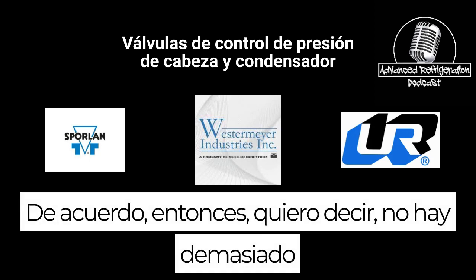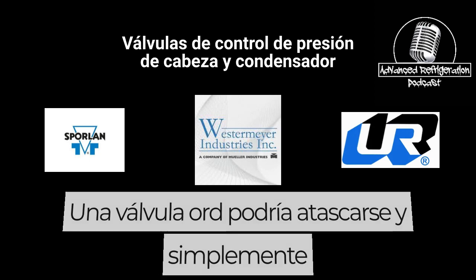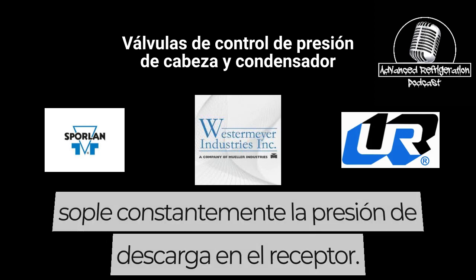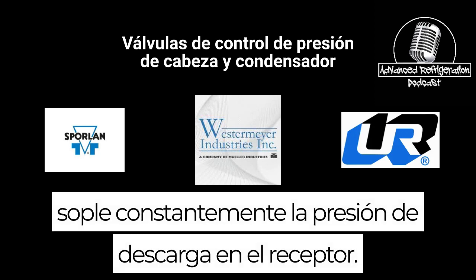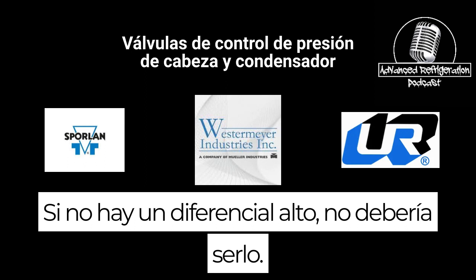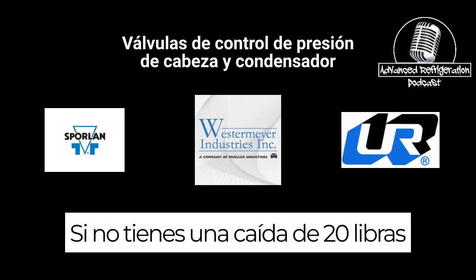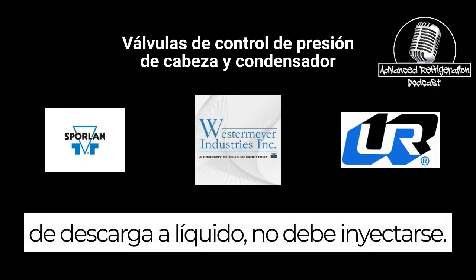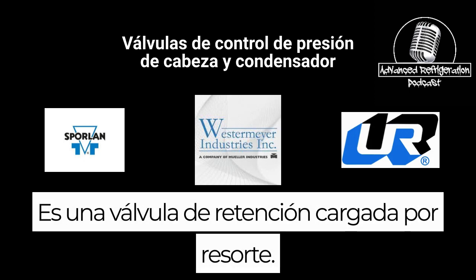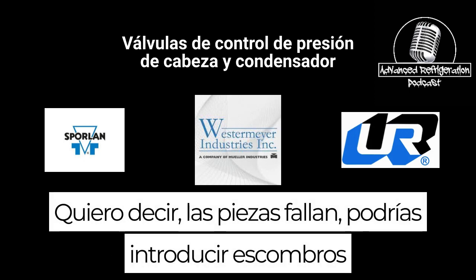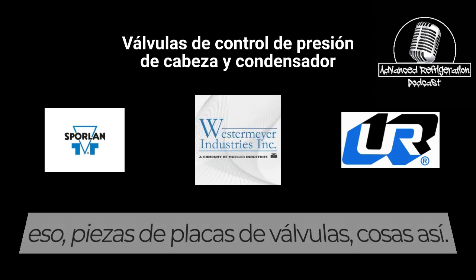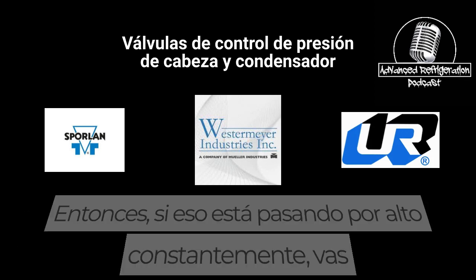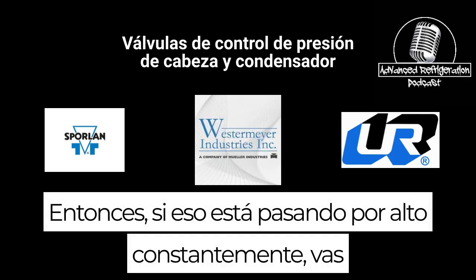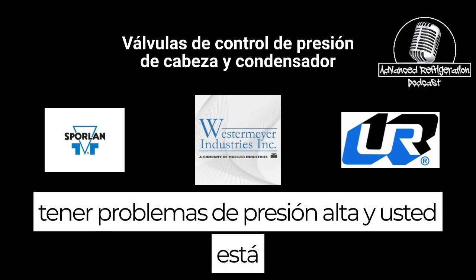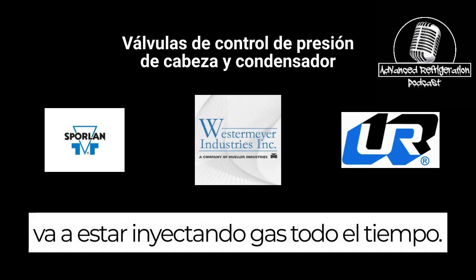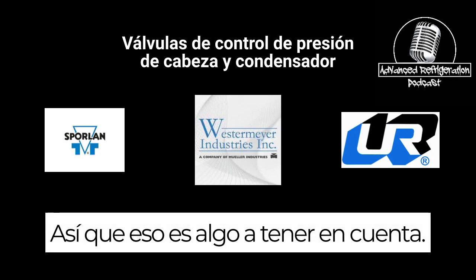Okay, so I mean, there's not too much to go wrong with this. An ORD valve could stick and just constantly blow discharge pressure into the receiver. If there's not a high differential, it shouldn't be. If you don't have a 20 pound drop from discharge to liquid, you shouldn't be injecting. It's a spring loaded check valve. I mean, parts fail, you could get debris in it, pieces of valve plate, stuff like that. If that is constantly bypassing, you're going to have high head pressure issues and you're going to be injecting gas all the time. So that's something to look out for.